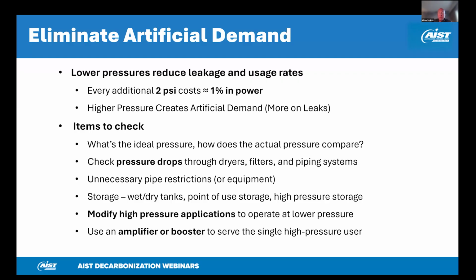There's lots of pressure drop through the system. Most people think it's in the piping and distribution system, but typically it's through dryers and filters and point of use components that are undersized. And one of the things you can do is utilize storage throughout the system to reduce the pressure drop from the air moving through the piping system. And we'll talk about that a little bit in the next few slides.